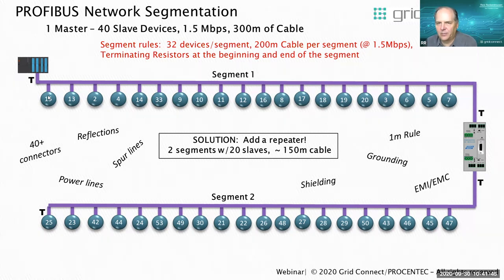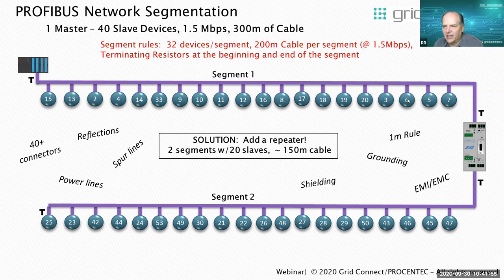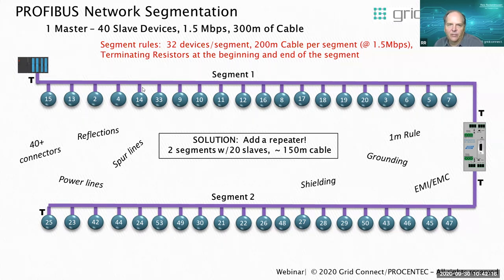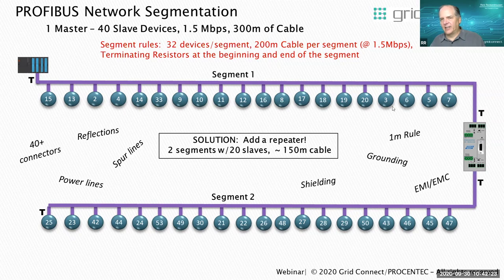The issue with big networks with long segments and a lot of devices is that if one device fails, the whole segment fails. Also confusing: if we have an error at address 13, the devices at the other end of the bus are the ones that will have problems, because the further away you are from the problem in PROFIBUS, the worse it gets. If you shorten those segments and get fewer devices per segment, you will have a more reliable and robust PROFIBUS network.